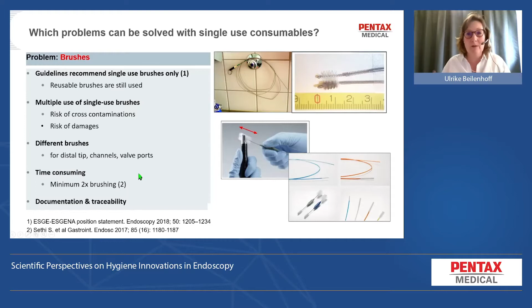If we reprocess endoscopes, we need different brushes for the distal tip, for the channels, for the valve ports, and also the time is not really defined. There are multiple brushing cycles recommended, minimum twice brushing cycles. And again, if you use reusable brushes, you also have the problem with the documentation and the traceability.